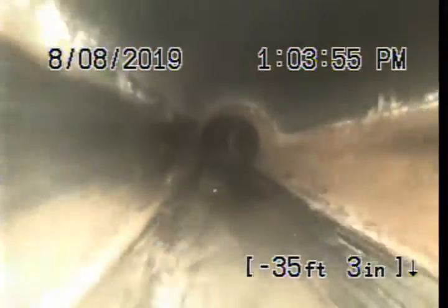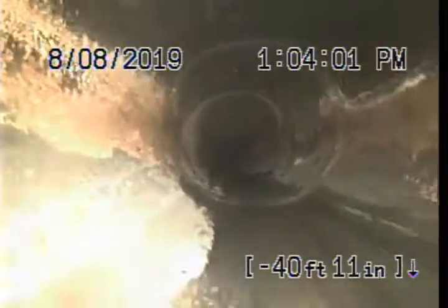It's a typical occurrence. Basically what's happening here is that the pipe has been mis-sloped, either when they were hanging the line or when they were running it underground, they didn't put it deep enough. So you have this section of the line here that's constantly holding water and debris. And that's going to need to get fixed. It's basically a backup hazard, and especially being under a building, it just creates an issue where things can get caught up in it much more easily.